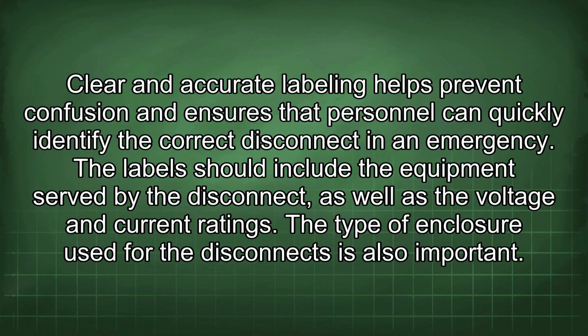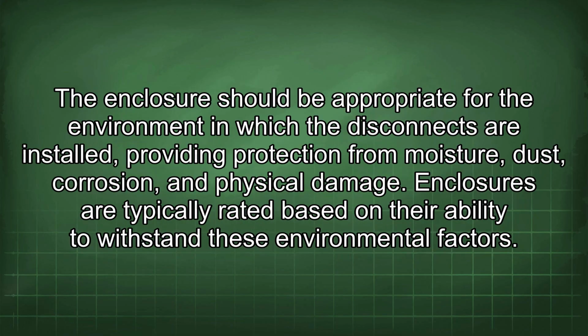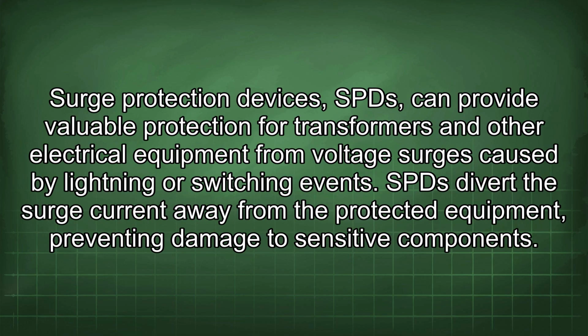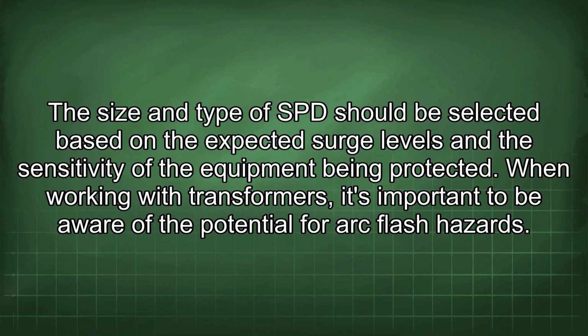The type of enclosure used for the disconnects is also important. The enclosure should be appropriate for the environment in which the disconnects are installed, providing protection from moisture, dust, corrosion, and physical damage. Enclosures are typically rated based on their ability to withstand these environmental factors. Surge protection devices, SPDs, can provide valuable protection for transformers and other electrical equipment from voltage surges caused by lightning or switching events. SPDs divert the surge current away from the protected equipment, preventing damage to sensitive components.